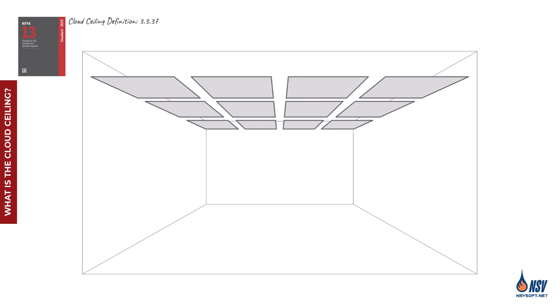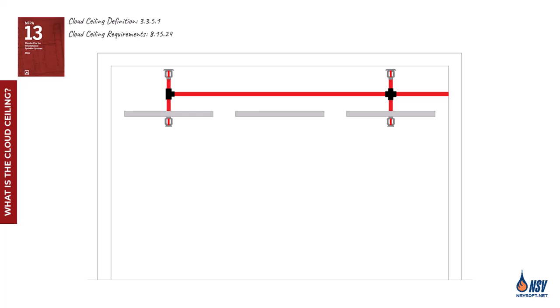According to NFPA 13, a cloud ceiling refers to any horizontal ceiling system installed in a single plane with open gaps to the structural elements above on two or more sides. In the 2016 edition of NFPA 13, cloud ceiling requirements were officially added to the standard, introducing allowances that permit sprinklers above the ceiling to be omitted.